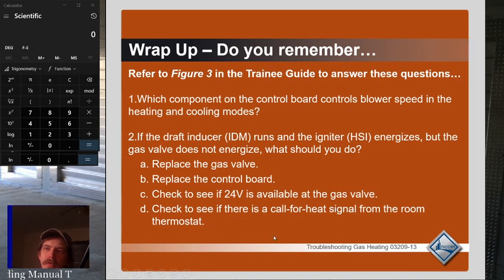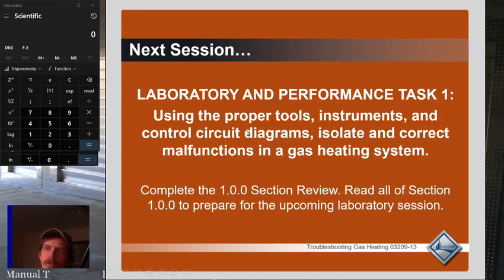If the gas valve does not come on, you're going to want to check to see if there's 24 volts at the gas valve. If you do have 24 volts at the gas valve, you'll want to double check your connections and check the coil of the gas valve, but odds are if you have 24 volts at the gas valve but the valve does not come on, then the gas valve is bad. You will have to replace it. But first, make sure that there's 24 volts at the gas valve.